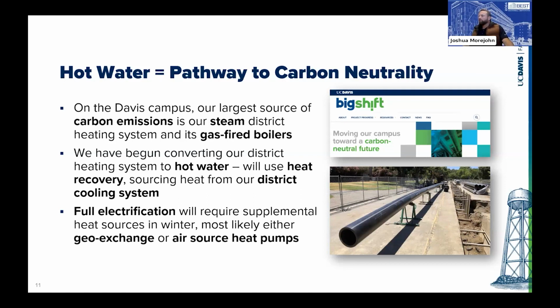This also shows the pipelines we're putting in. They're a high temperature HDPE pipe called PERT pipe, which we landed on after looking closely at alternatives, like the European standard thin wall steel pipe, pre-insulated, that other campuses have used. This pipe had some advantages: one, corrosion resistance, and water chemistry not being as much of an issue as with thin wall steel pipe. Also cost and speed of installation, going in a lot faster compared to welding thin wall steel, which requires specialized labor as well.